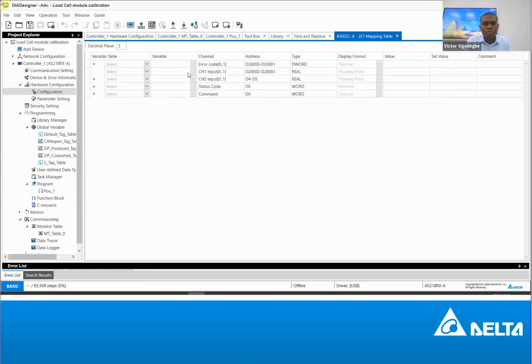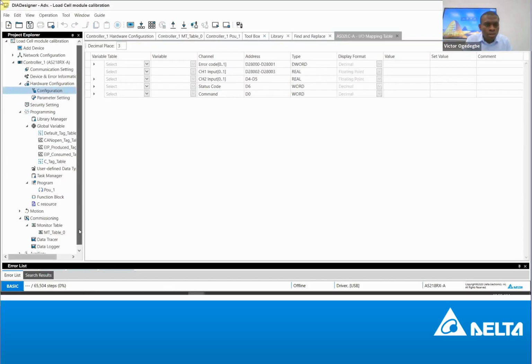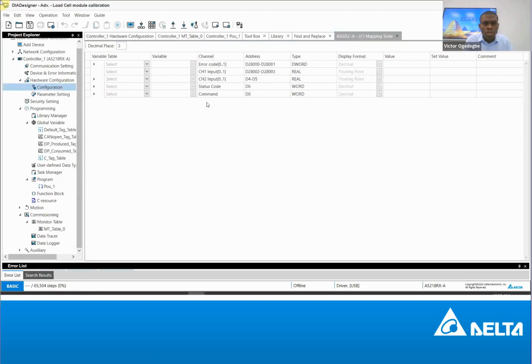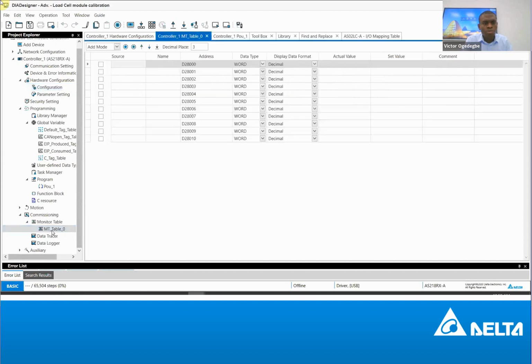But the assignment by the CPU does not cover all those multiple registers. With the TO and FROM instructions, you can get access to all those control registers and do what you want with them, especially if you have a system where you want very high precision, then you can use that to command it. Let's go online and see which value we have. What I did is set up a monitor table and put these addresses there. So let's go to the table. What do we have on this table?